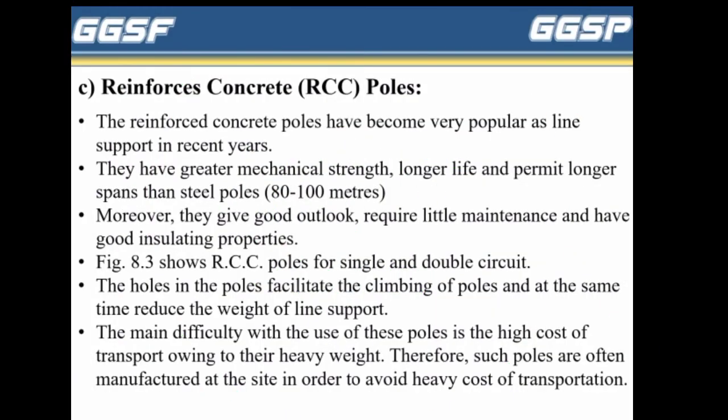Reinforced concrete poles. The reinforced concrete poles have become very popular as line supports in recent years. They have greater mechanical strength, longer life, and permit longer spans than steel poles, which is 80 to 100 meters. Moreover, they give a good outlook, require less maintenance, and also have good insulating properties. Figure 8.3 shows the RCC poles for single and double circuit.